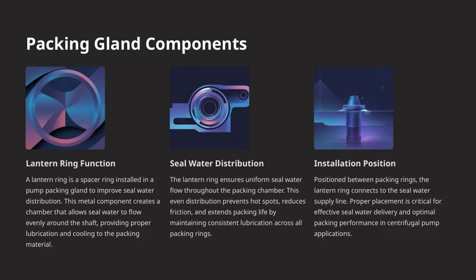Let's take a closer look at the packing gland components, starting with the lantern ring. A lantern ring is essentially a spacer ring that we install in the pump packing gland. Its main function is to improve the distribution of seal water around the shaft. This metal component creates a chamber that allows the seal water to flow evenly, which is crucial for proper lubrication and cooling of the packing material.